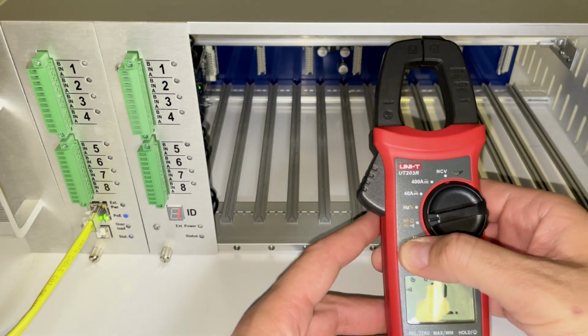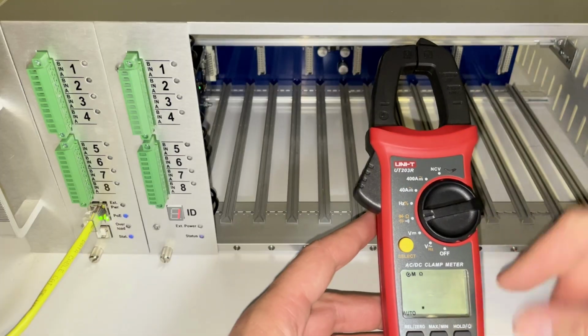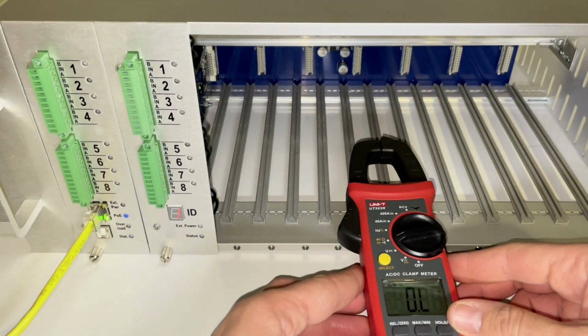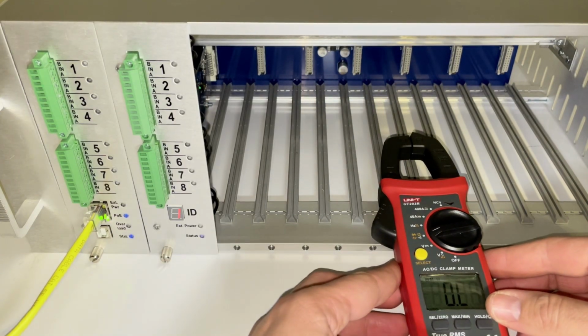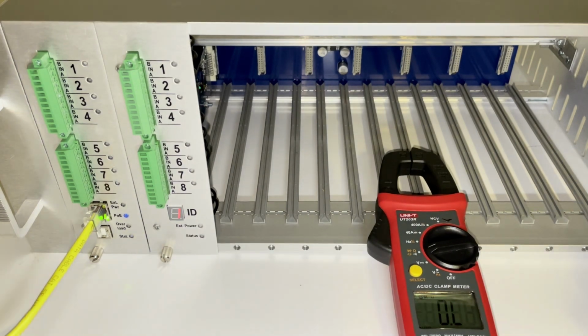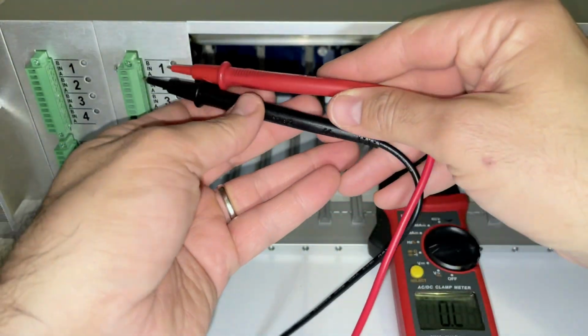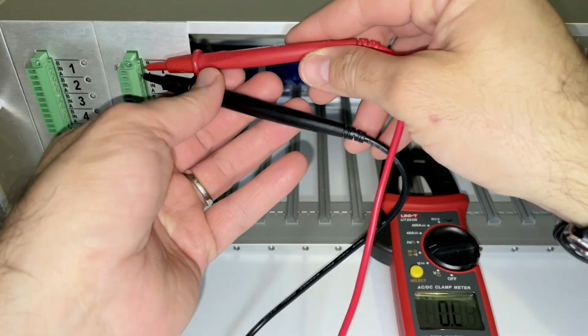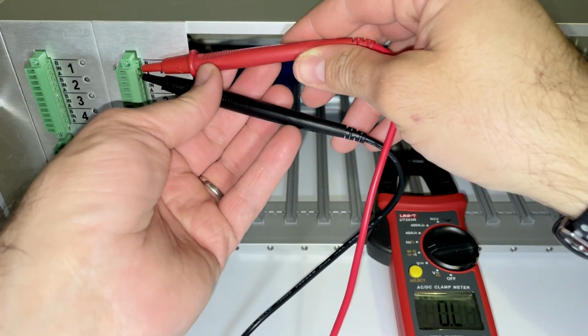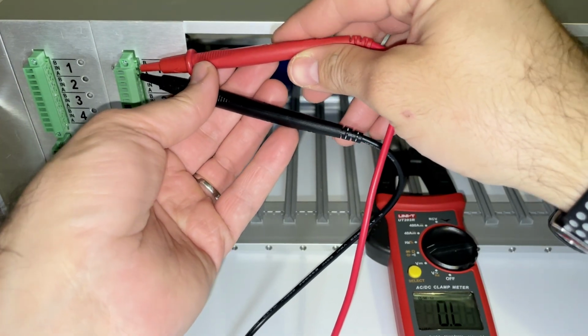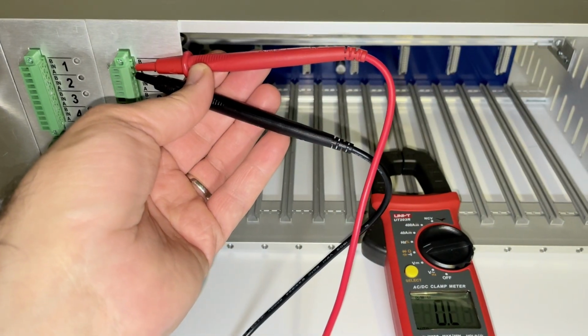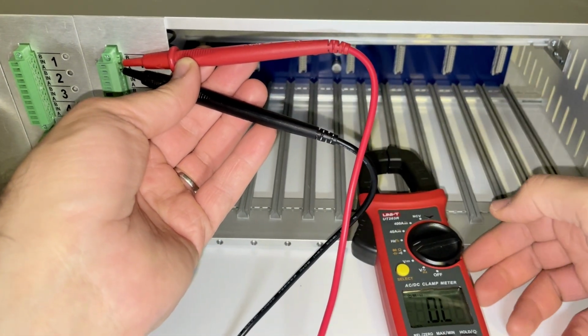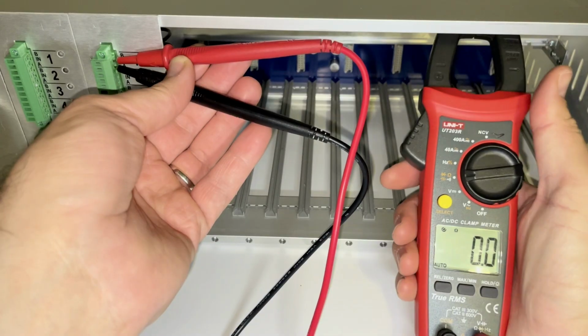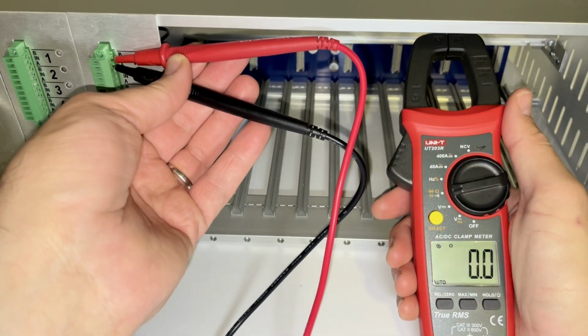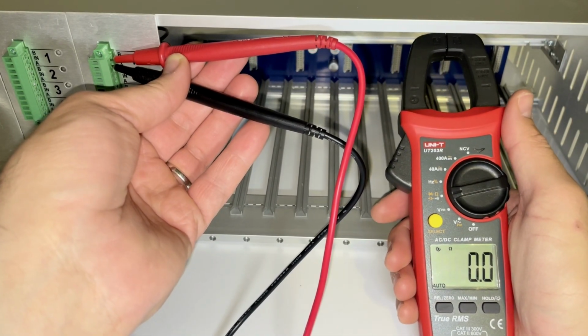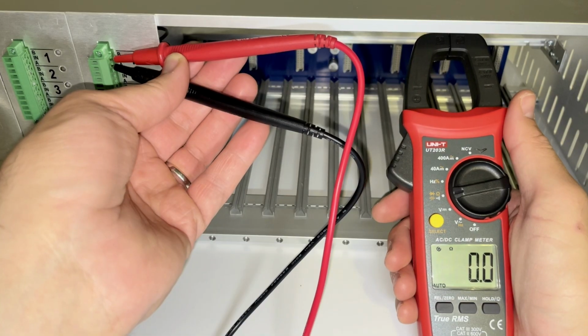This method provides a clear indication of whether the relay contacts are opening and closing correctly by measuring changes in electrical resistance. Start by testing the normally open contact. Place the black probe on the common terminal and the red probe on the normally open terminal of the dry relay. In the idle state, the multimeter should display either OL or a very high resistance value, indicating that the circuit is open. Trigger the system using a test fob or access code and wait for the relay to activate.